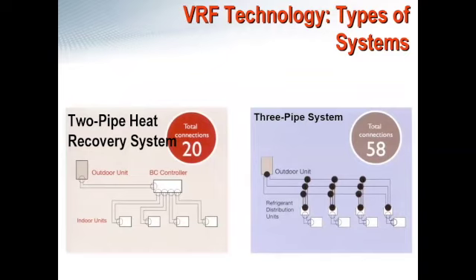Really, the only thing we want to take a look at here is the total connections. The way we like to look at it, and I know a lot of the other manufacturers in the market look at it, is that any connection point is a possible point of failure. It's something that the manufacturer really doesn't have very much control over. Most of the time, there aren't very many leaks or defects with the units themselves. It's when the units get installed that there's a possibility of failure at the connection point.